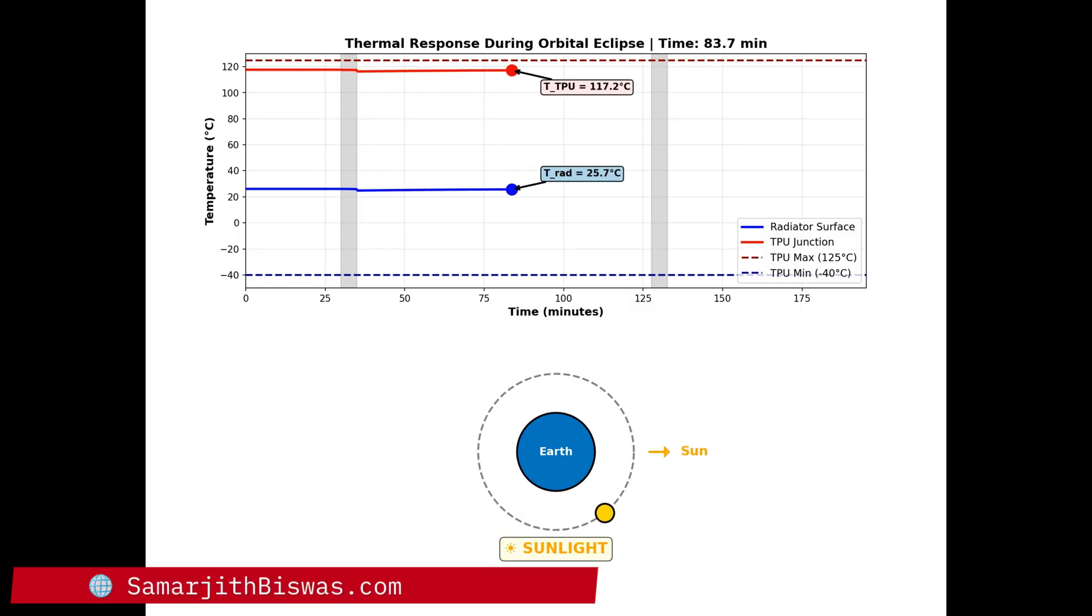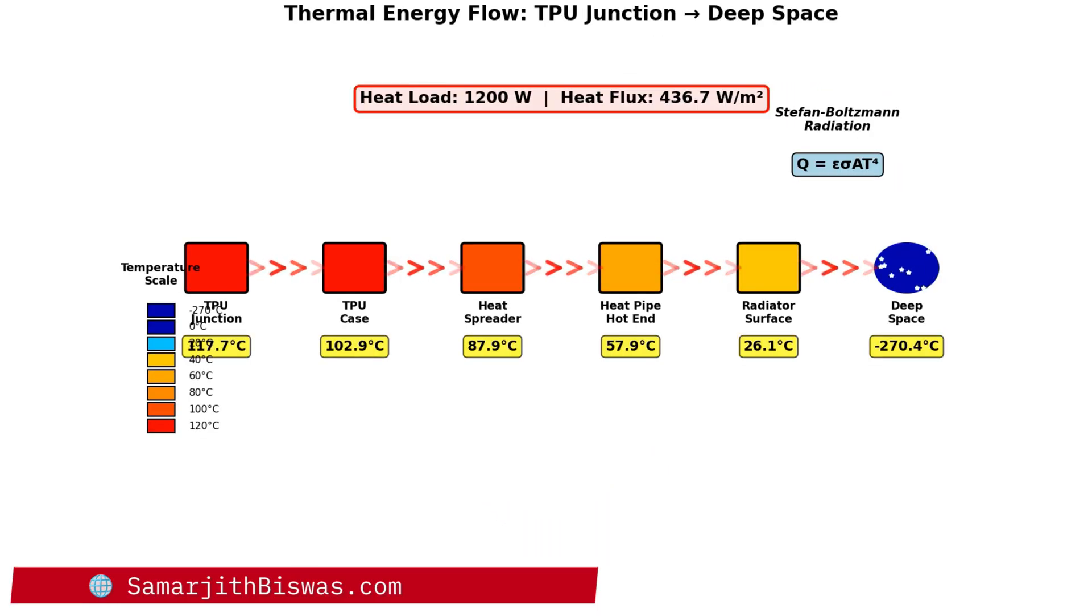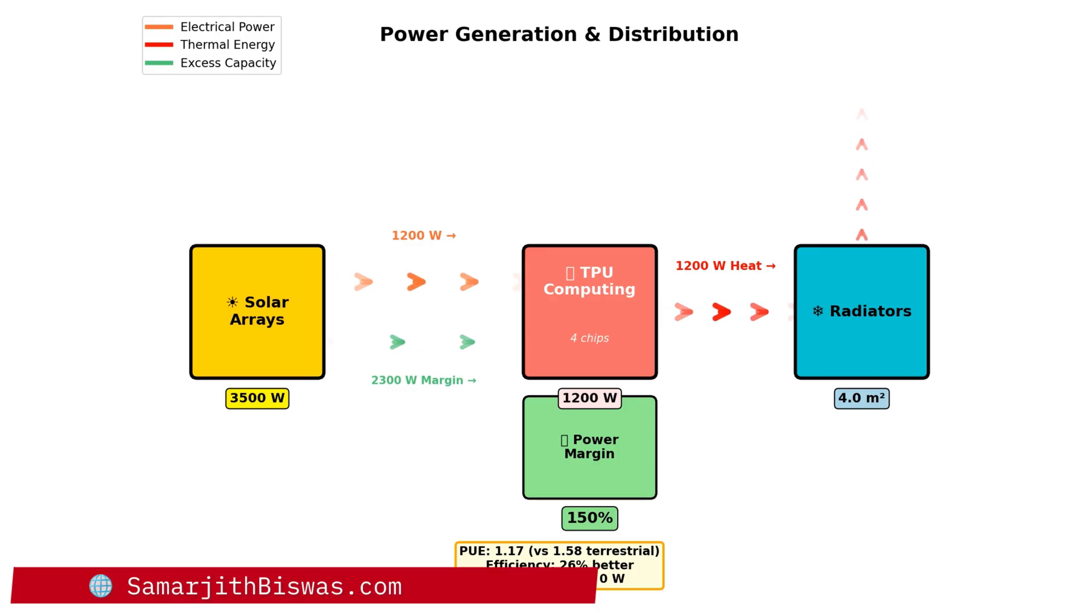The efficiency numbers tell the real story, right? Power usage effectiveness: 1.17. Ground-based data centers average 1.58, so that's about 26% better efficiency. Zero water consumption, zero direct carbon emissions, and basically unlimited cooling capacity.